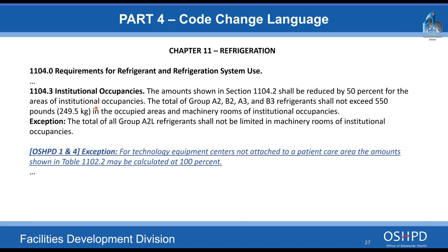We've got a little bit outside the envelope on this one. What we're trying to do here is we say for technology equipment centers not attached to a patient care area, the amounts shown in table 1102.2 may be calculated at 100%. So in general, in the chapter 11 on refrigeration, when you have an I occupancy, it says the amounts of refrigerant you can use in these facilities, you've got to take that max allowable and cut it in half.